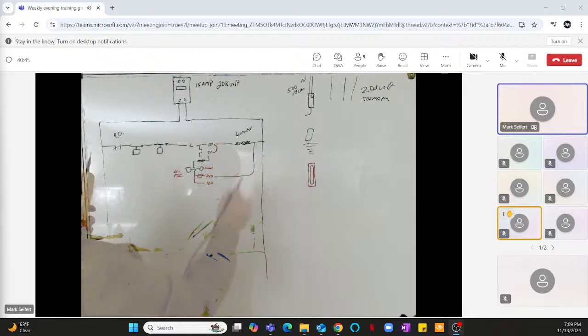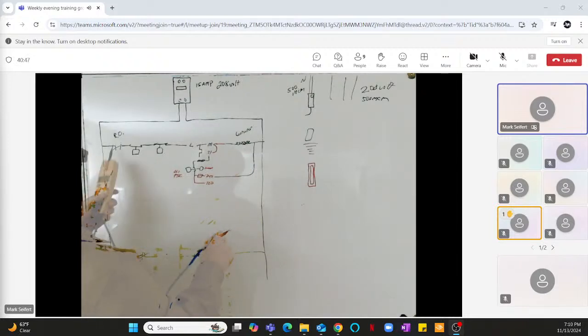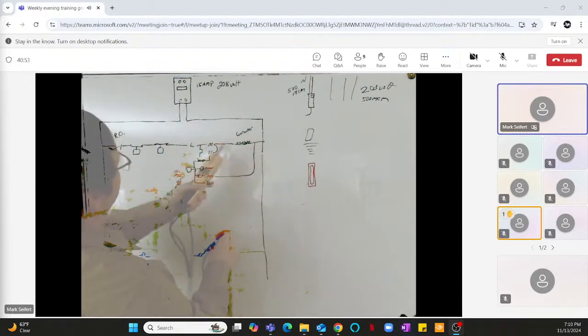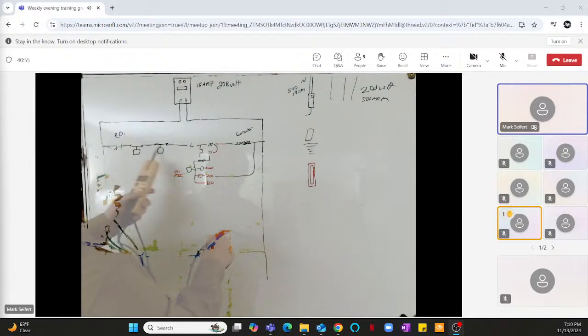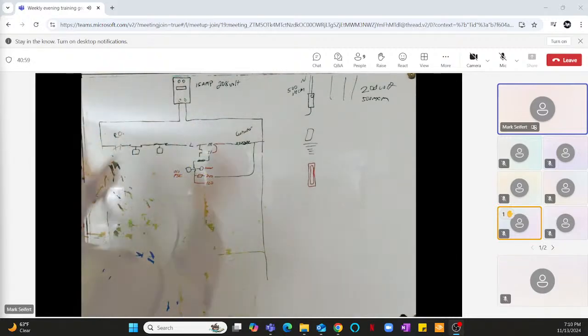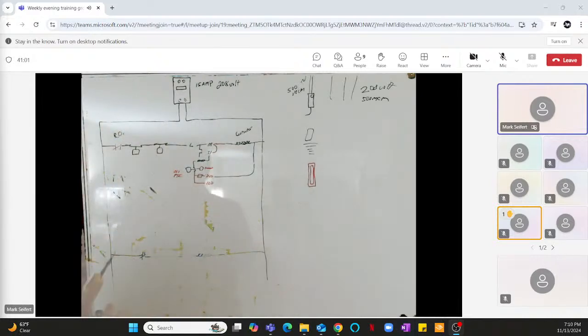But you can't use ground. Because, again, if you check the ground, you're going to have power everywhere. It's going to always have power. You got power there. You got power there. The whole thing's going to be powered up. So you can't use ground unless you're trying to figure out if you've got power to the circuit. So that makes sense.